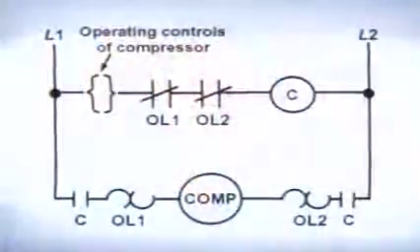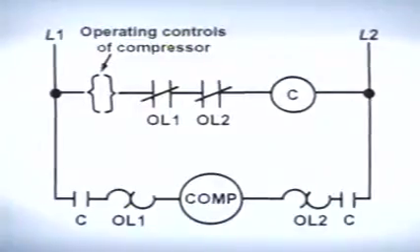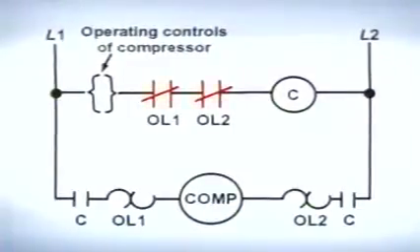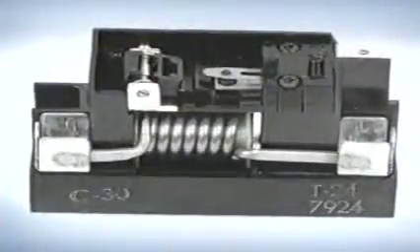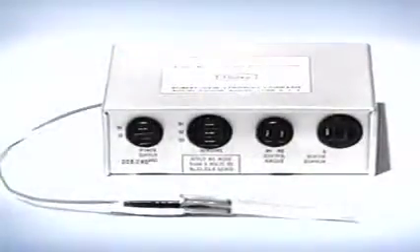The other type of commonly used overload is the pilot duty overload. Unlike the line brake overload, the pilot duty overload breaks the control circuit, not the power circuit of the device being controlled. Notice that the overload contacts are located in series with the contactor coil, not the compressor itself. Three common types of pilot duty overload are the current type, the magnetic overload, and the electronic overload.